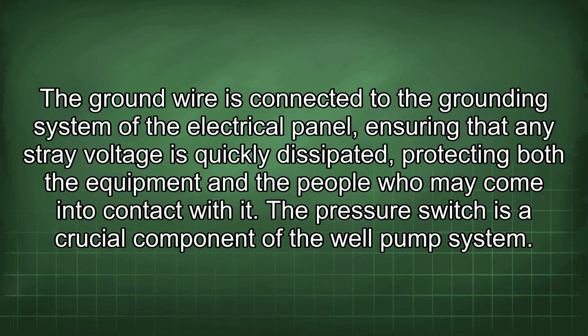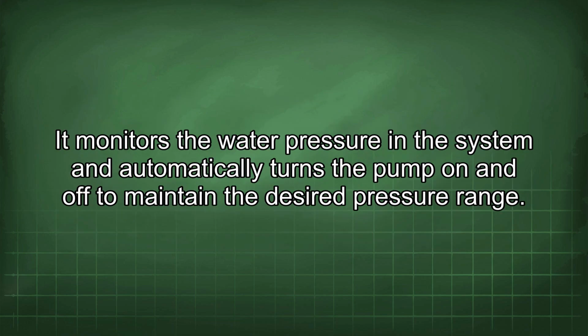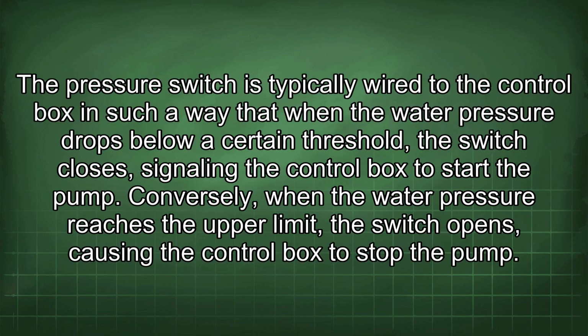The pressure switch is a crucial component of the well pump system. It monitors the water pressure in the system and automatically turns the pump on and off to maintain the desired pressure range. The pressure switch is typically wired to the control box in such a way that when the water pressure drops below a certain threshold, the switch closes, signaling the control box to start the pump. Conversely, when the water pressure reaches the upper limit, the switch opens, causing the control box to stop the pump.